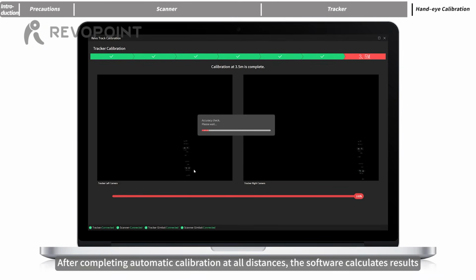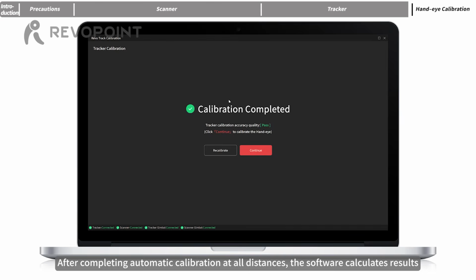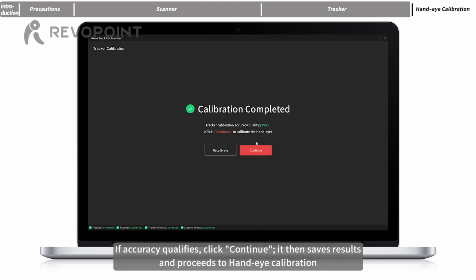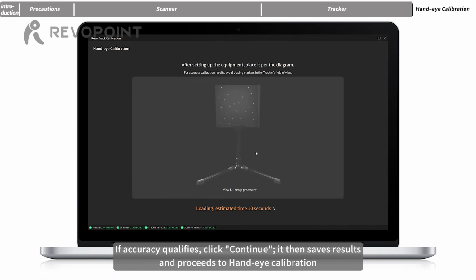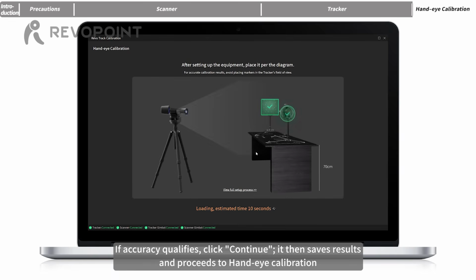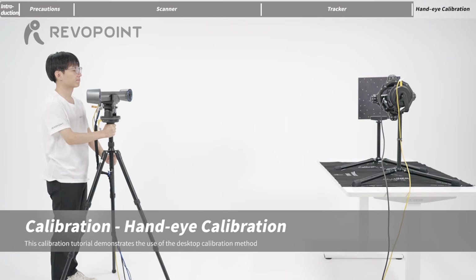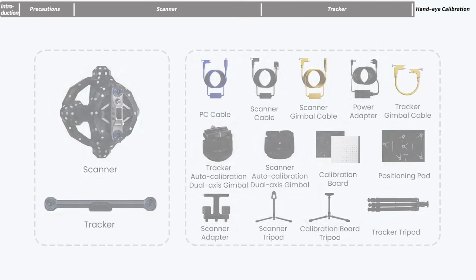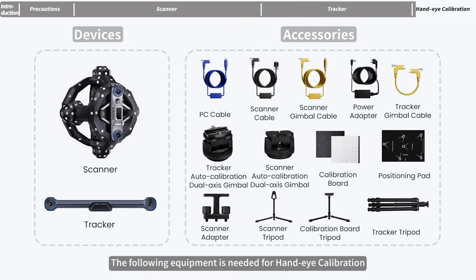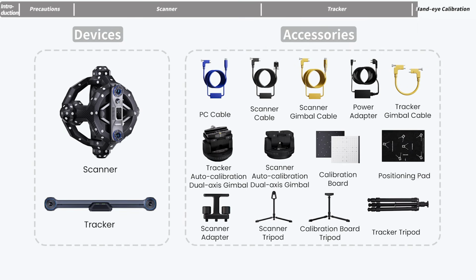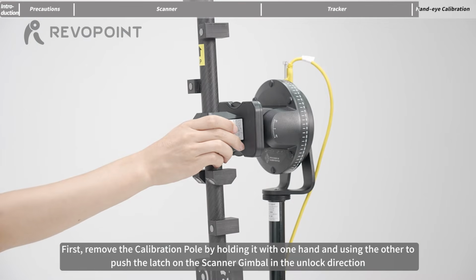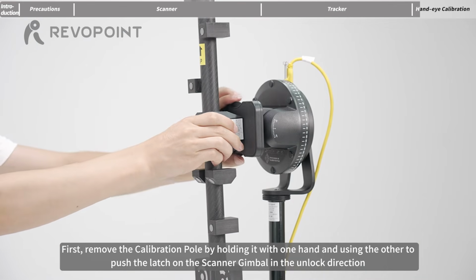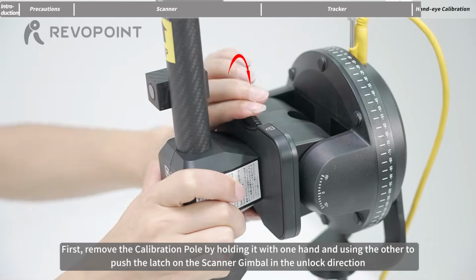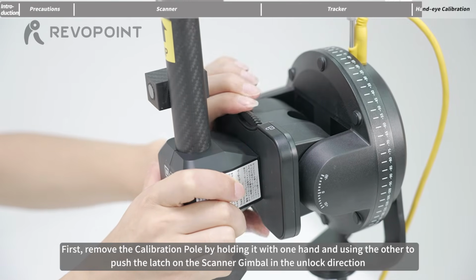After completing automatic calibration at all distances, the software calculates results. If accuracy qualifies, click Continue. It then saves results and proceeds to hand-eye calibration. The following equipment is needed for hand-eye calibration. First, remove the calibration pole by holding it with one hand and using the other to push the latch on the scanner gimbal in the unlock direction.